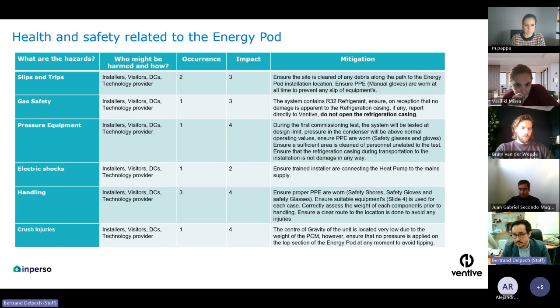In terms of gas safety, because we have R32 in the system, it's not pressurized that much. Even if it's released, it's going to be released in a contained environment. But ideally, we don't want that to happen because we would have to ship another unit. So for the refrigeration casing, please ensure that there is no damage to it. When you receive it on site, take some photos and send us the photos, so we can ensure, for your own benefit as well, that there is no damage done by the end user. Never open the refrigeration casing. The only time the refrigeration casing can be opened is when the Ventive employees are on site with the installer.